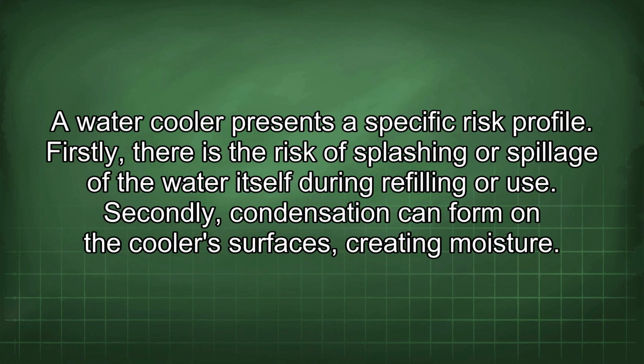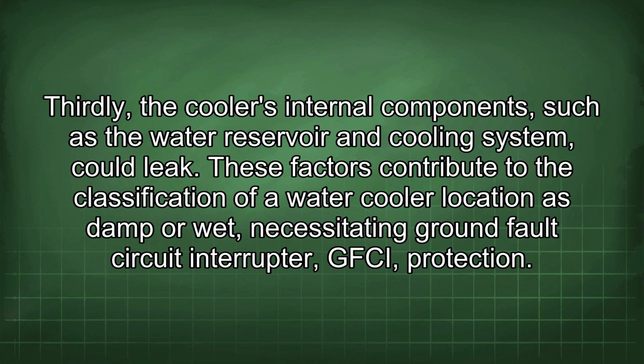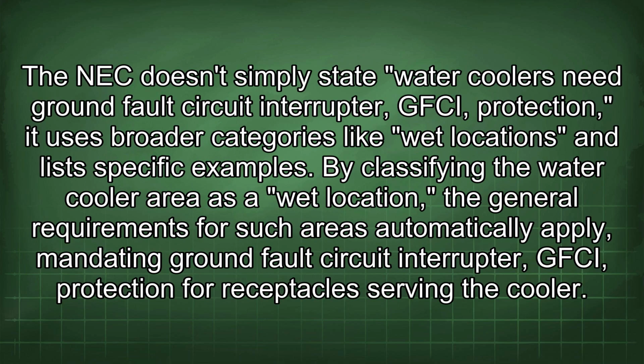A water cooler presents a specific risk profile. Firstly, there is the risk of splashing or spillage of the water itself during refilling or use. Secondly, condensation can form on the cooler's surfaces, creating moisture. Thirdly, the cooler's internal components, such as the water reservoir and cooling system, could leak. These factors contribute to the classification of a water cooler location as damp or wet, necessitating GFCI protection. The NEC doesn't simply state water coolers need GFCI protection.